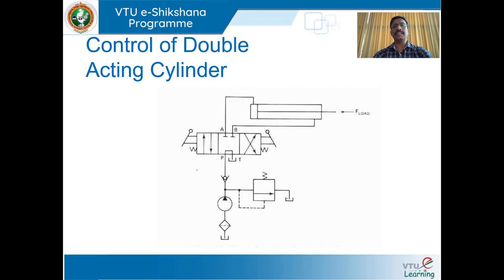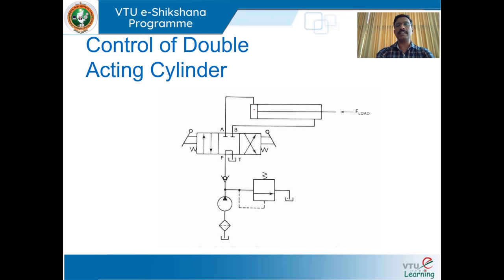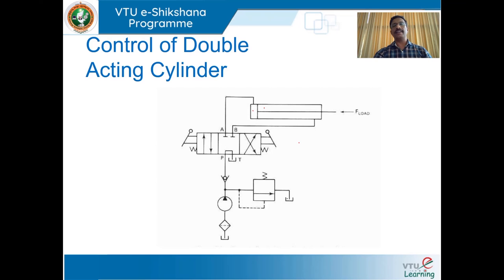Next, we shall discuss the control of a double acting cylinder. Here we shall discuss how a four-way, three-position directional control valve is used to control the double acting cylinder. Double acting cylinder means control pressure is applied on either side of the piston — that is on the blank end and also on the rod end — and both extension and retraction take place hydraulically.